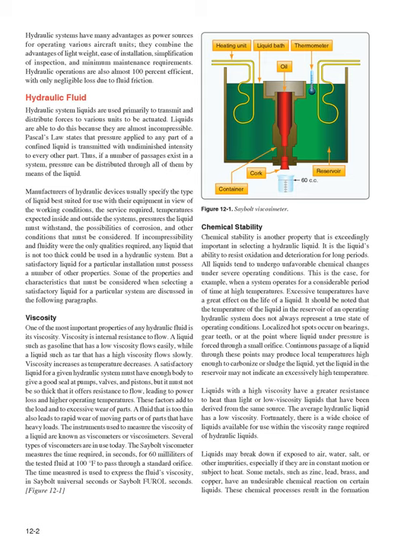Viscosity increases as temperature decreases. A satisfactory liquid for a given hydraulic system must have enough body to give a good seal at pumps, valves, and pistons, but it must not be so thick that it offers resistance to flow, leading to power loss and higher operating temperatures. These factors add to the load and to excessive wear of parts. A fluid that is too thin also leads to rapid wear of moving parts or of parts that have heavy loads. The instruments used to measure the viscosity of a liquid are known as viscometers or viscosimeters.